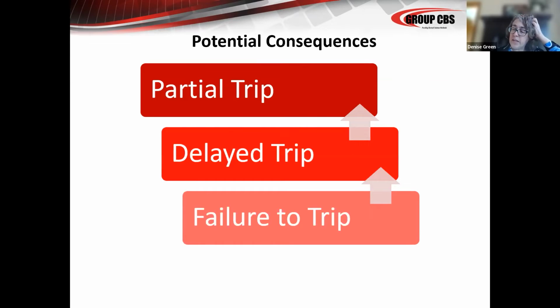So I was involved in a situation, a real life situation, where a customer had continued failure of their vacuum interrupters on their breakers. Originally, they were working with the manufacturer. They thought there was a bad batch. No one could figure out why the bottles failed. If you lose vacuum in an interrupter and that breaker opens in a fault situation, the gap between the contacts inside that interrupter is not sufficient to break the circuit, and you will have a full arcing event.